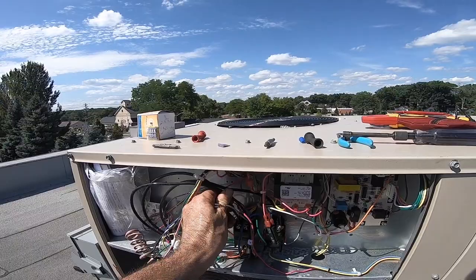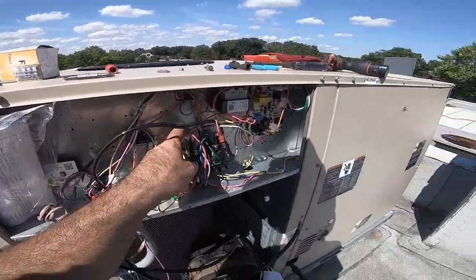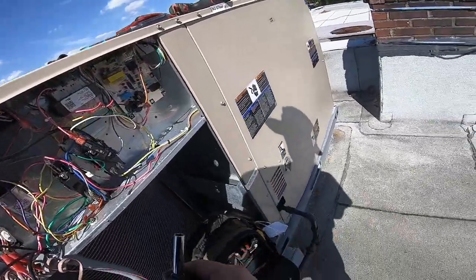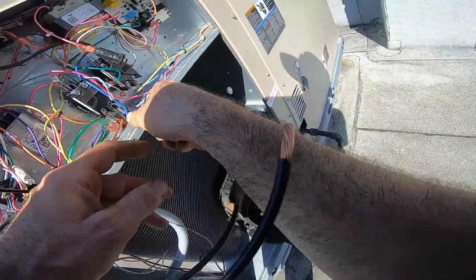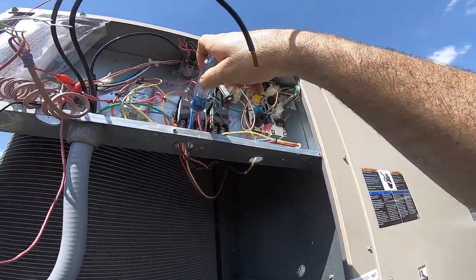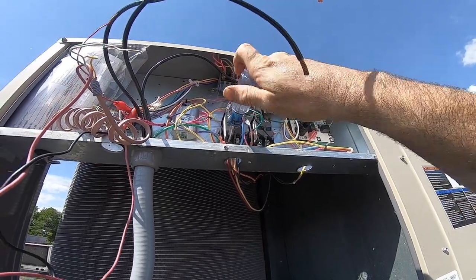Okay, it's out of my way. These are out of my way now. All right, so the top here has three reds. This yellow wire is super tight, no slack. But now let's see the bottom. This is where it's burning. Is the connection loose? That moves back and forth, but it could just be burnt. But it looks like this may just be a little loose. It wasn't tightened. I guess I'll tighten it down.